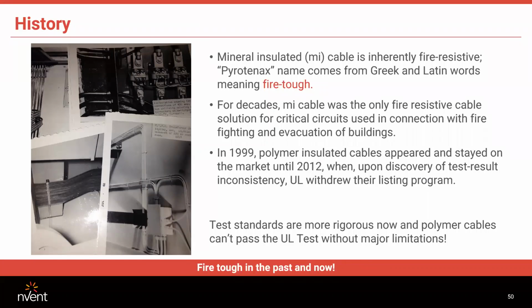all of these cables, with the exception of MI, have run into listing issues. In the late 90s, the polymer cables were first introduced to the market, and then they were delisted in 2012 because UL found a big inconsistency in their testing. They realized they had not tested the cable properly, and when they tested it properly, they found the fail ratio to be, I believe, around 70%, which is just completely unacceptable.